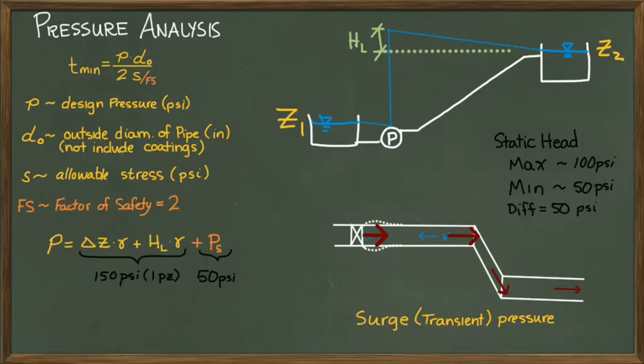Therefore, a water system pumping two pressure zones at a time with the same static head criteria will need to account for 200 psi of operating pressure with the same 50 psi of surge, making the design pressure in this example 250 psi. A similar procedure can be applied to systems that pump three pressure zones at a time.